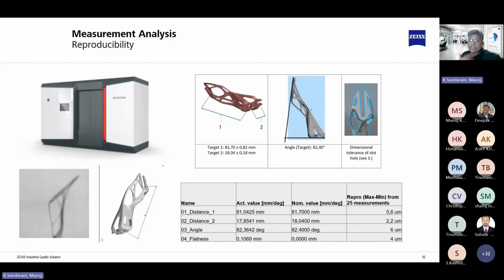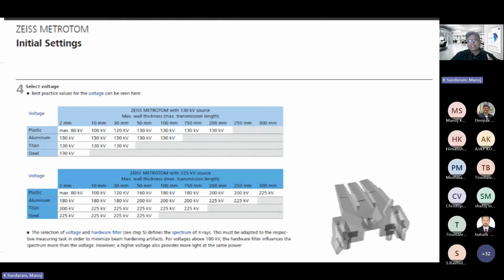So we will demonstrate. How much can you penetrate? This is a key topic in CT. Plastic up to 300 millimeters, aluminium 200 to 220 millimeters, titanium up to 100 to 150, steel up to 30 to 40 millimeters. They are cumulative wall thicknesses, not the size of the part. The part size itself can be 300 cube, 350 cube, or even 500 cube actually.